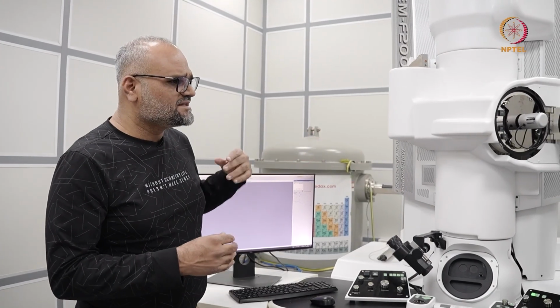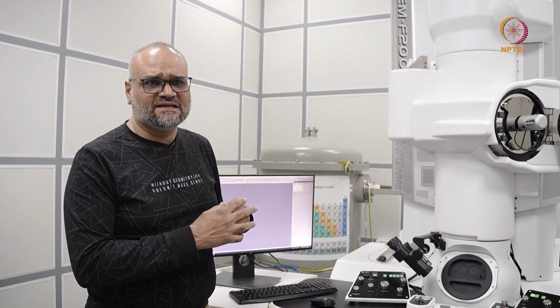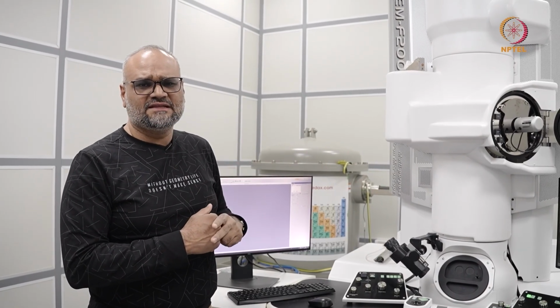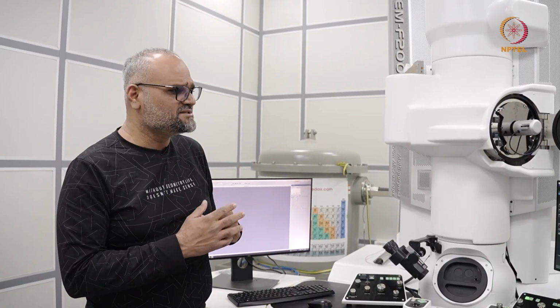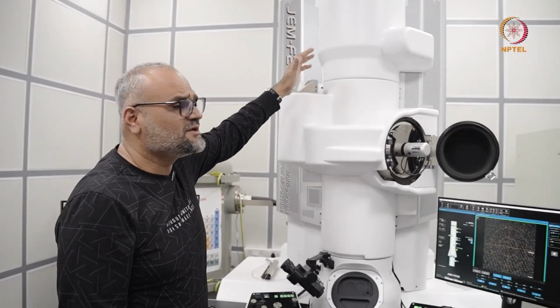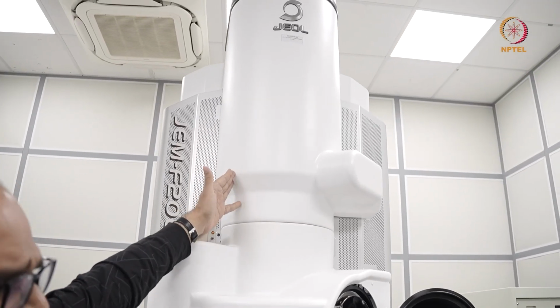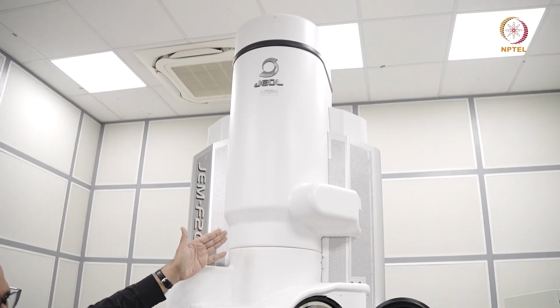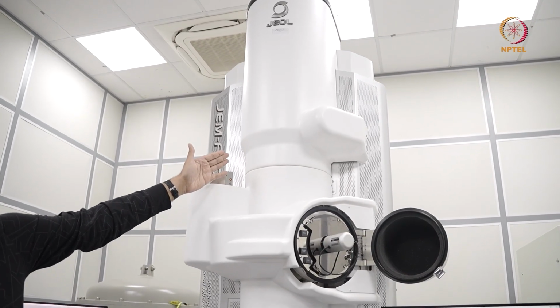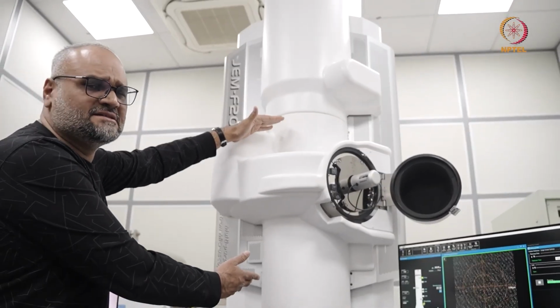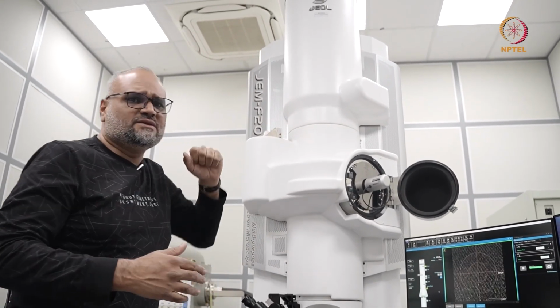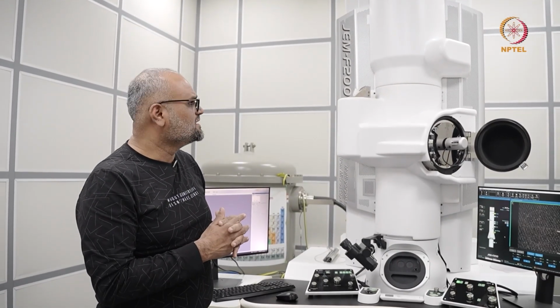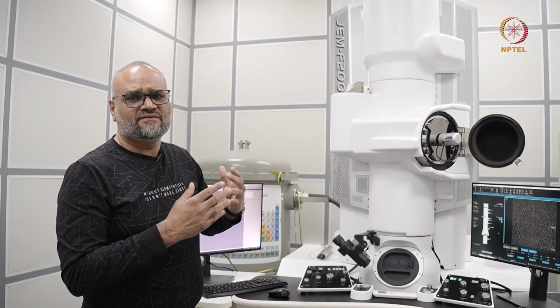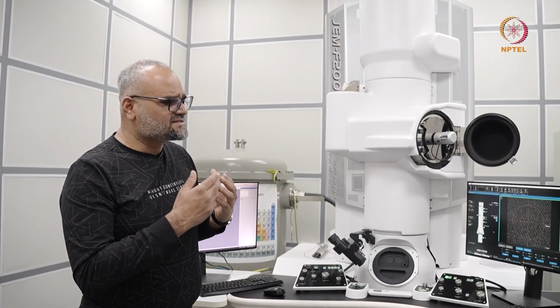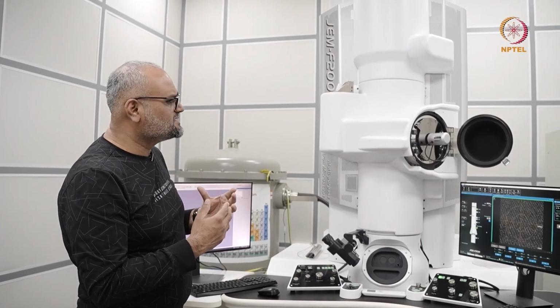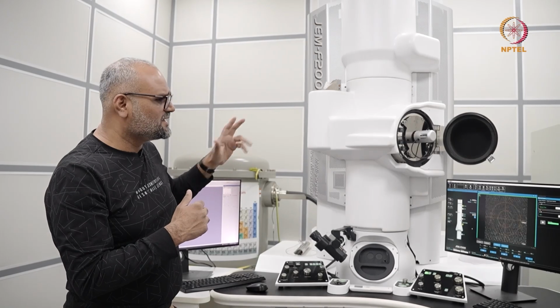And once the oil diffusion pump achieves a vacuum of something in the range of 10 to the minus 5 Pascal, you have 3 sputter ion pumps, or the other manufacturer, Thermo Fisher, calls them the ion getter pumps. So you have a 200 liter sputter ion pump which is connected to the gun chamber here, and in between the gun and the column you have another 150 liter sputter ion pump, and on the column where the specimen area is, you have another 300 liter sputter ion pump. So the idea is, in a cold field emission microscope, which is extremely sensitive to ultra high vacuum, to have more stable emission, you would want to maintain as good vacuum for as long as possible. And this is achieved with a combination of several sputter ion pumps as well. So in this system, you have 3 of them.